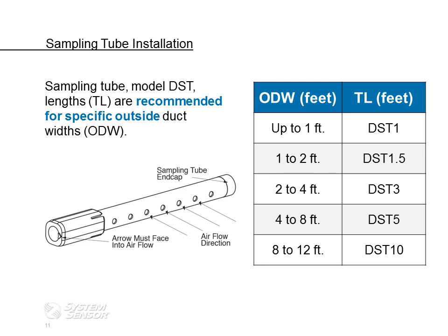One thing to make sure of is that the arrow indicates the holes are oriented into the airflow, which is very important. And the second thing that's required is that the end cap on the sampling tube must be in place for it to function.